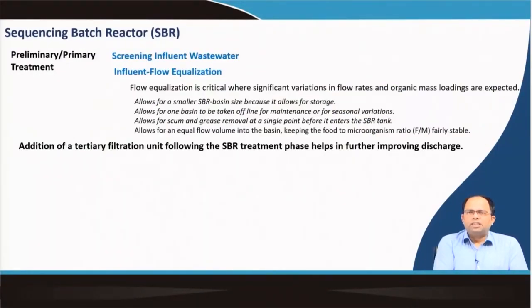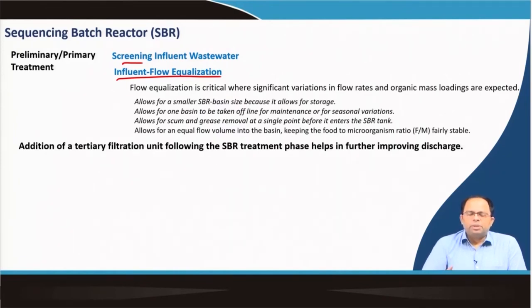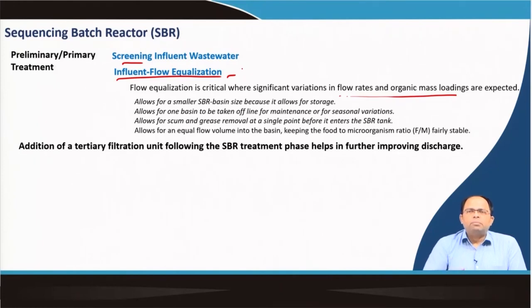When operating a sequencing batch reactor, we also need to do some preliminary or primary treatment. We screen the influent wastewater so that plastics or other floating matter do not enter the SBR chamber, and we also need flow equalization. SBRs cannot handle too much load or too much varying flow, so a flow equalization tank is critical. The total organic loading has to be within a certain value, making flow equalization a mandatory process before the SBR.